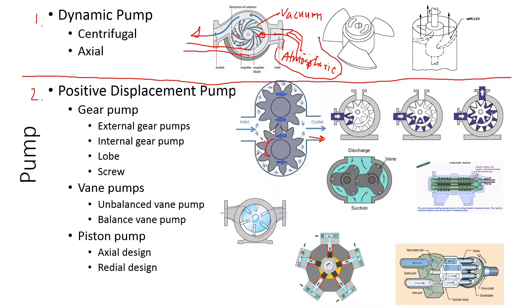These two gears meet externally, which is why this is called an external gear pump. An internal gear pump has one gear sitting inside another — a small gear inside a big gear. The gear pump and lobe pump are almost exactly the same, except for the shape of the gear. In a lobe pump, the gear looks more like a lobe, but they work exactly the same. The lobe pump can also be internal or external.